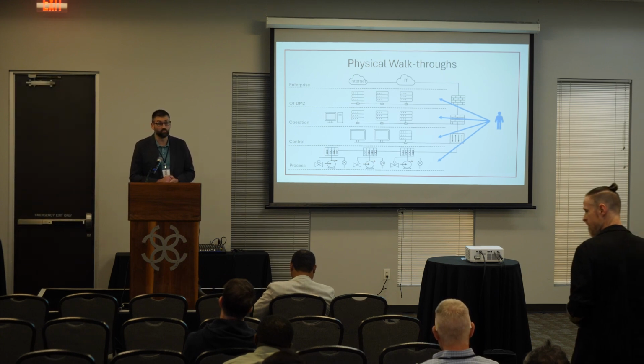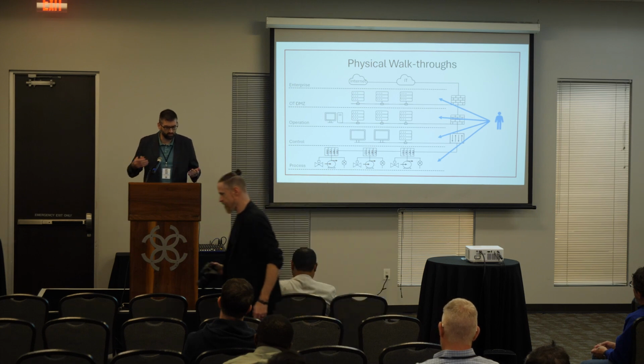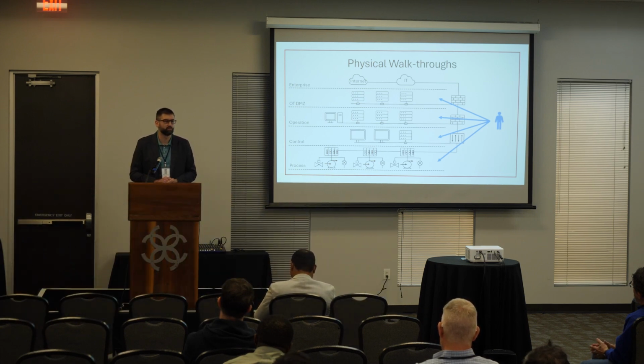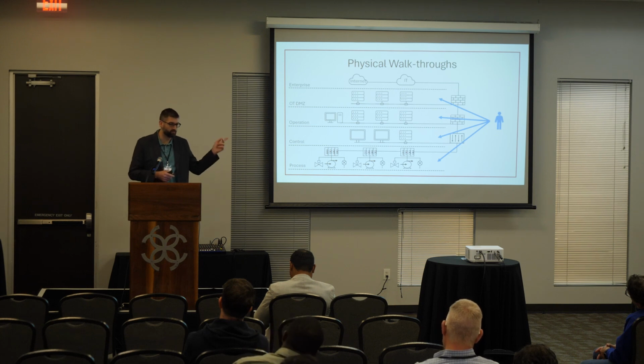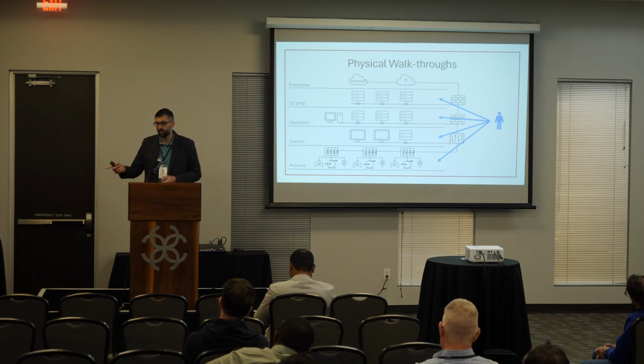Walked into a control room. We knew we had an HMI in there. Our passive monitoring asset management picked up that device. But when I walked into the control room, I noticed there were 2 Ethernet cables running out of the back of that PC. So I followed the first one over to the wall and traced it back. It went to the SCADA switch and tied into the SCADA servers. Great. Followed the other one and it went back over to the IT switch.